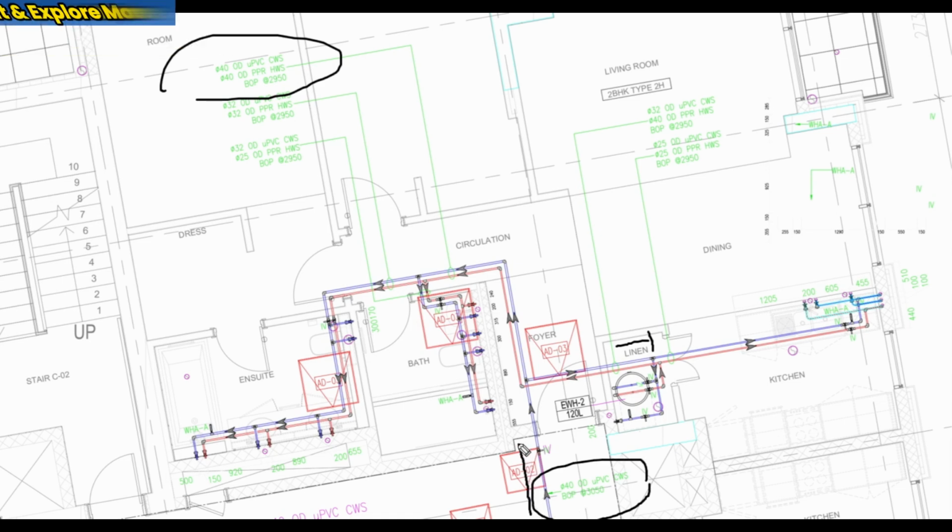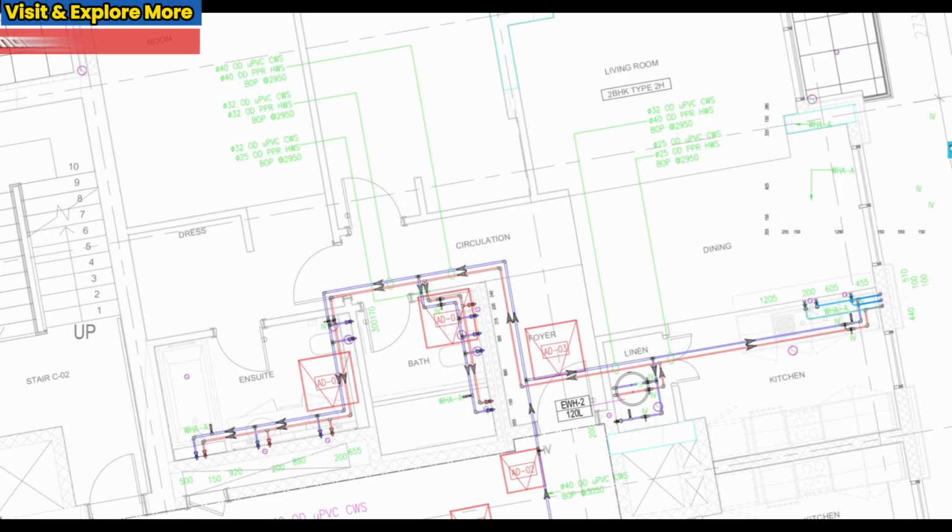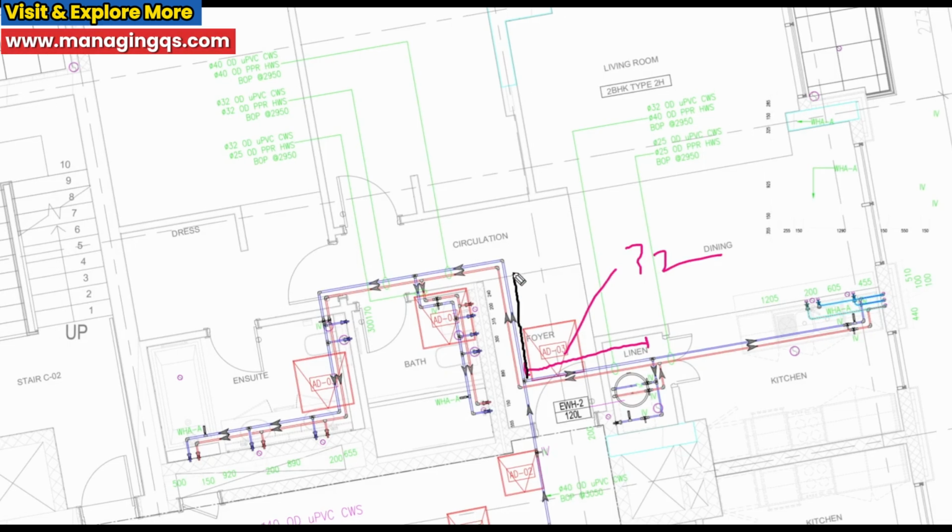So this pipe network is going through this direction and bending to the left side. So we have to confirm this entire blue color pipe network is the 40 diameter. Another conclusion is the 32 diameter ends from this reducing T up to this reducing T. So this is only 32 diameter. In this pipe, 40 diameter.